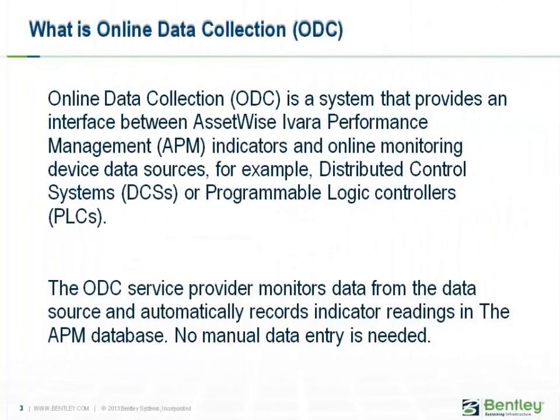What is Online Data Collection (ODC)? ODC is an interface between AssetWise iVara Performance Management indicators and Online Monitoring Device data sources — for example, Distributed Control Systems (DCS) or Programmable Logic Controllers (PLCs). When using ODC with an indicator, the ODC service provider monitors data from the data source and automatically records the indicator readings in the APM database. No manual data entry is needed.